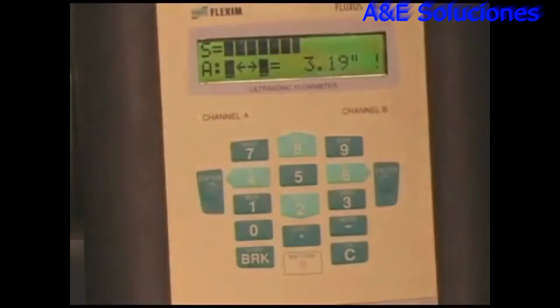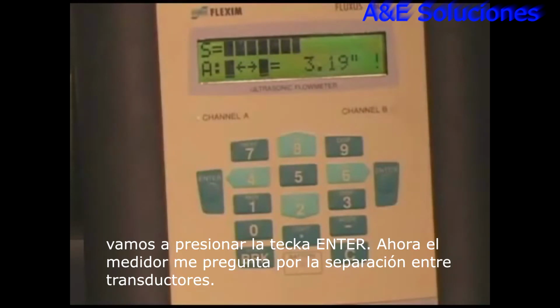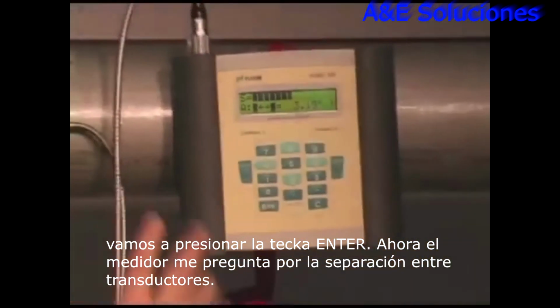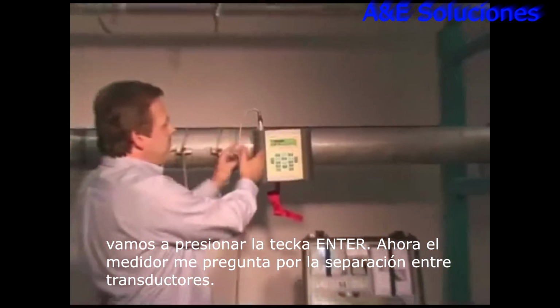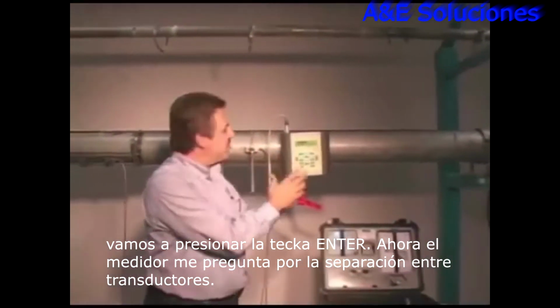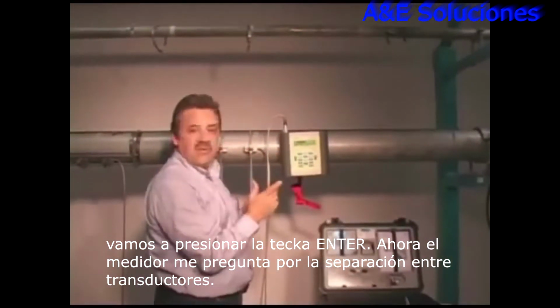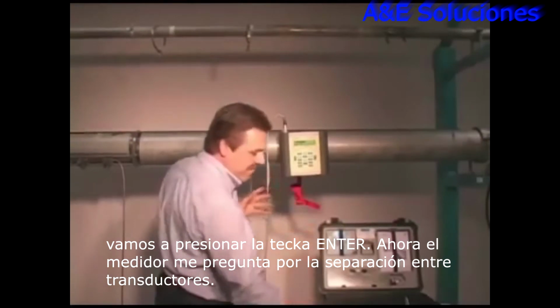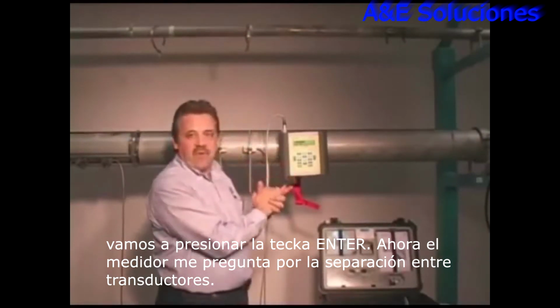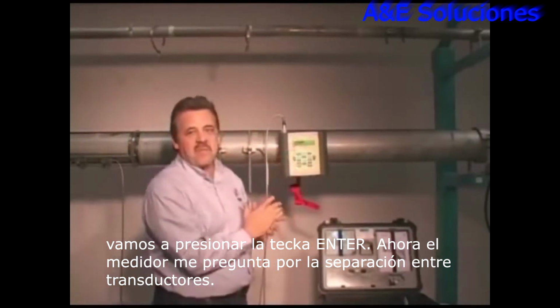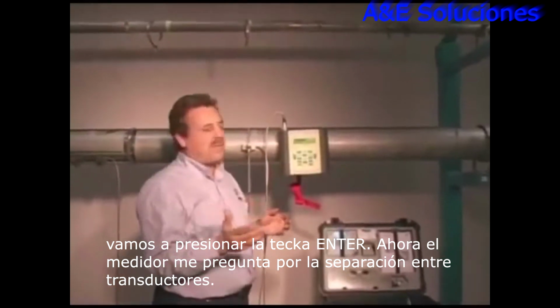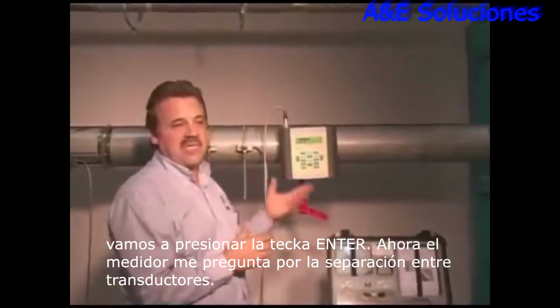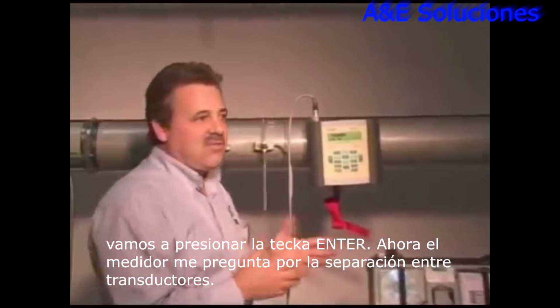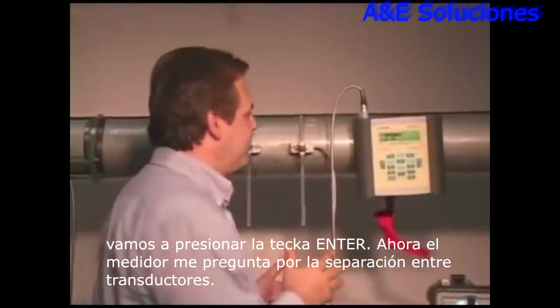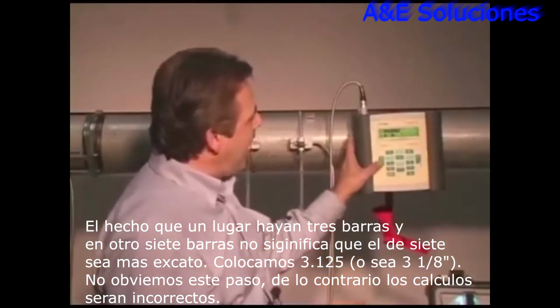You'll find yourself sort of rooting for the signal now, because you know that when you put this thing on the pipe, if you've got the 3+ bars of signal and you have a green light, you're going to do good. And the difference between having, say, 3 or 4 bars of signal and having 6 or 7 bars of signal does not mean that I'm going to have a more accurate reading because I have 7 bars of signal. You just have to be above the minimum level. Okay, so I like what I see.